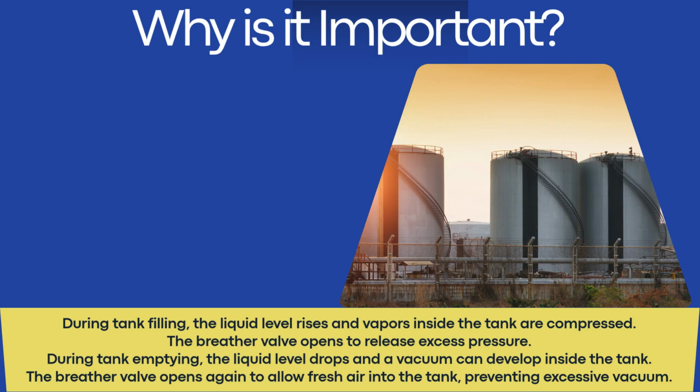Why is it important? During tank filling, the liquid level rises and vapors inside the tank are compressed. The breather valve opens to release excess pressure. During tank emptying, the liquid level drops and vacuum can develop inside the tank. The breather valve opens again to allow fresh air into the tank, preventing excessive vacuum.